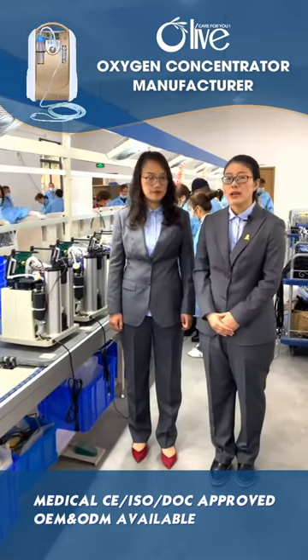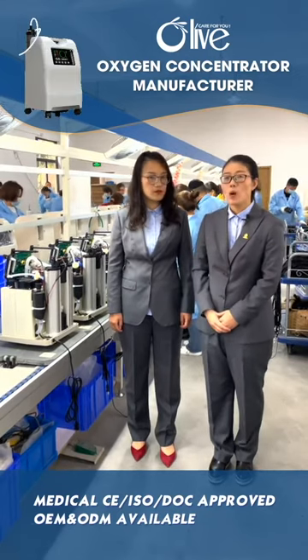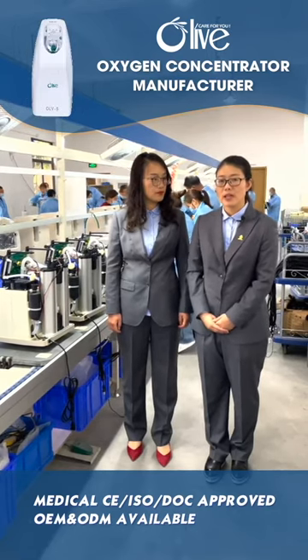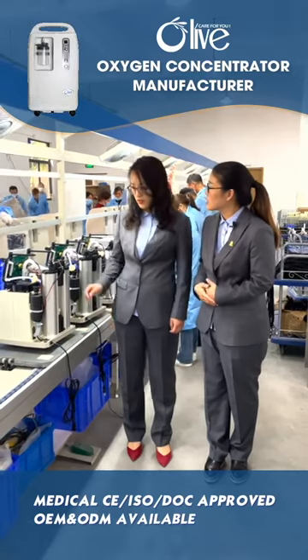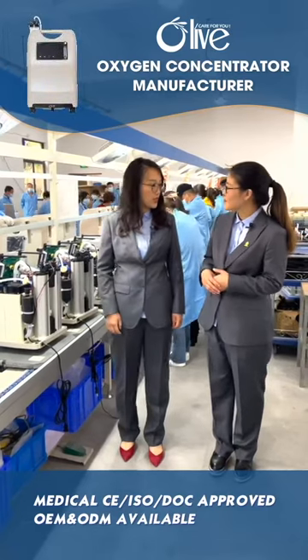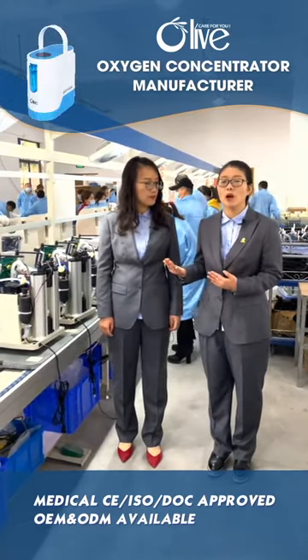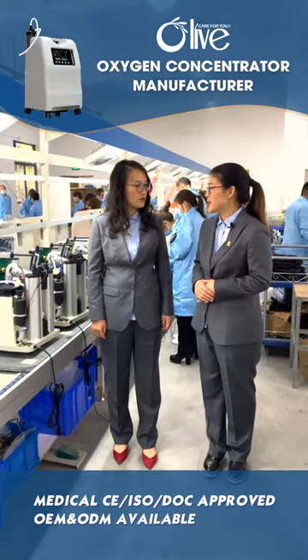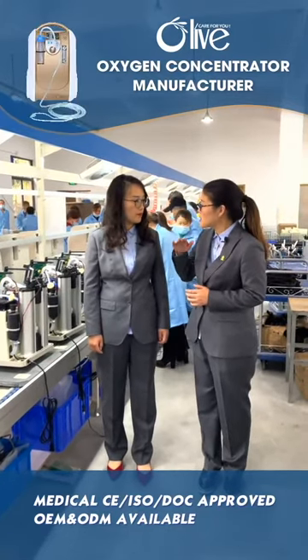Medical grade. In the market, there were two kinds of oxygen concentrators. One is the healthcare, we call it healthcare. Another is the medical oxygen concentrator, just like our 5 liter and 10 liter oxygen concentrators. This machine is medical grade, right? Yes, correct. The reason why we call it a medical oxygen concentrator is because it has high oxygen purity, above 93%.